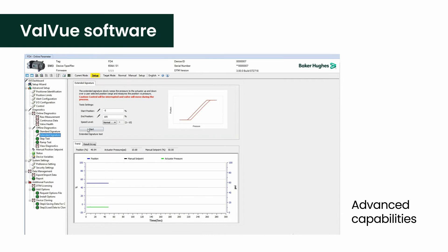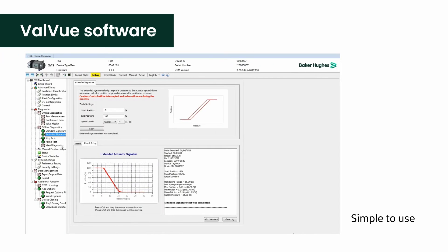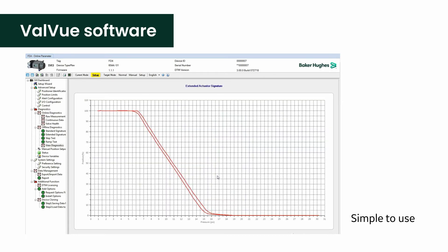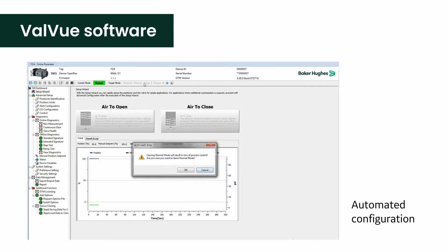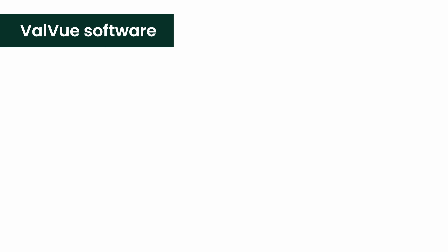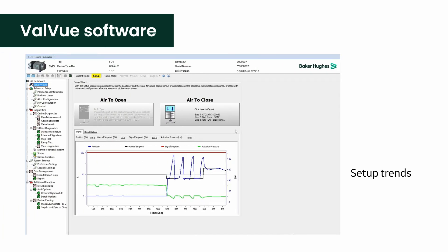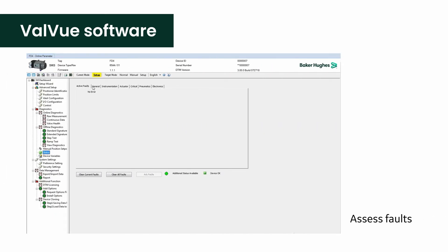SVI3's most impressive features are the digital capabilities you can tap into with our ValVue software and SVI3's Device Type Manager, or DTM. Full positioner setup and configuration can be executed through the simple DTM interface, which has enhanced graphics and tips that make the advanced features easier to use. A setup wizard gives the same automated configuration capabilities as the SmartCal feature on the device interface. You can set up trends, navigate continuous positioner diagnostics, and assess faults, all with the click of a mouse.